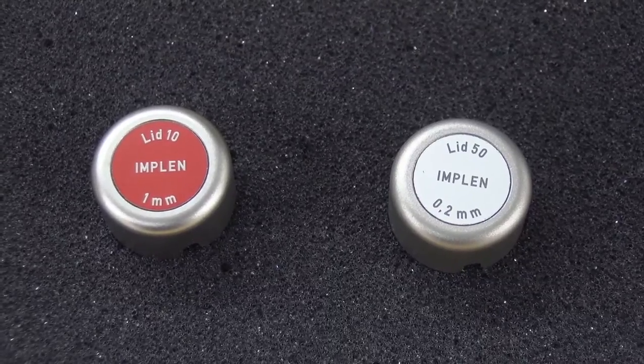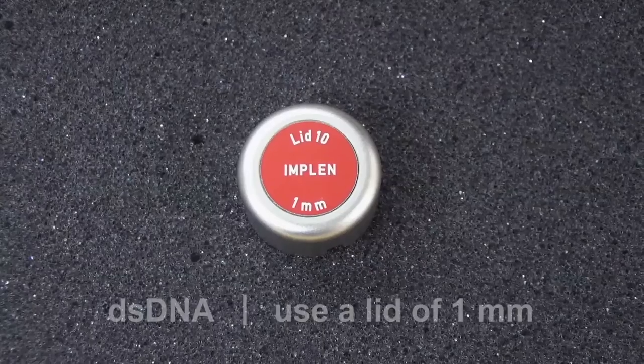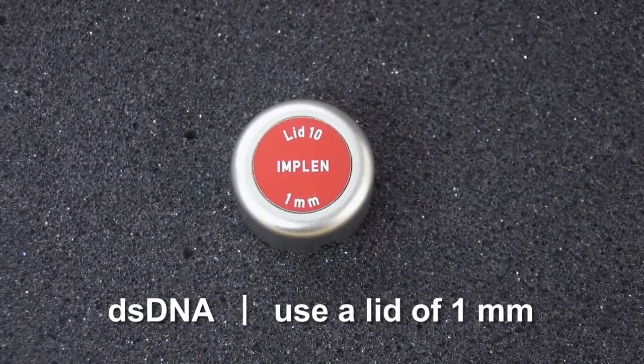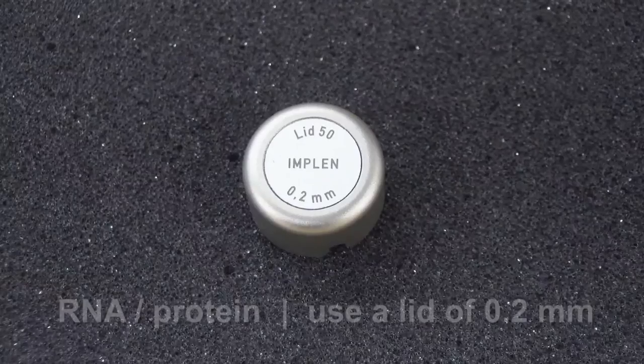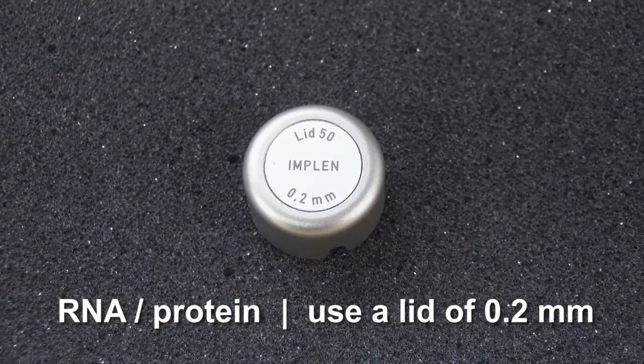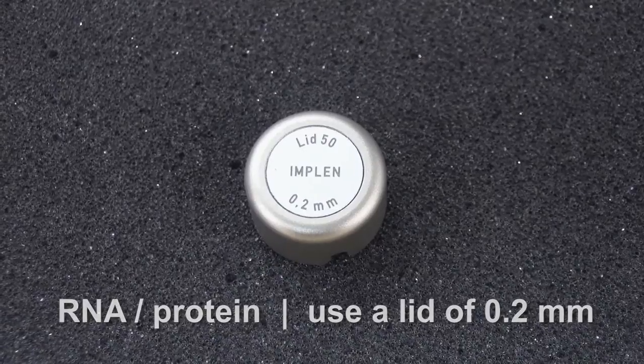4. Choose a proper lid based on the kind of sample. Use a lid of 1 millimeter path length for double-stranded DNA and use a lid of 0.2 millimeter path length for RNA or protein.